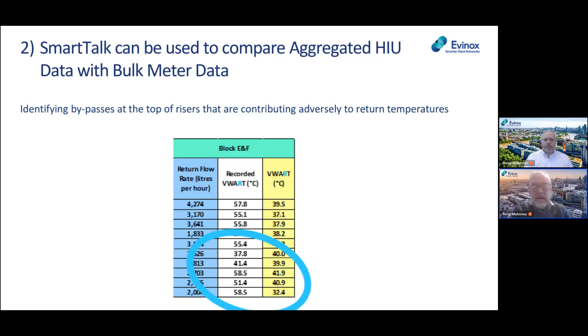When we further investigated this particular riser, we discovered there was a bypass open at the top. Closing that brought the actual return temperature down to where it should be.